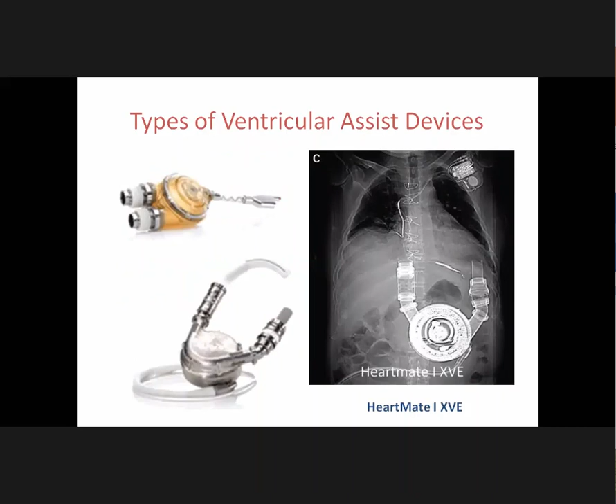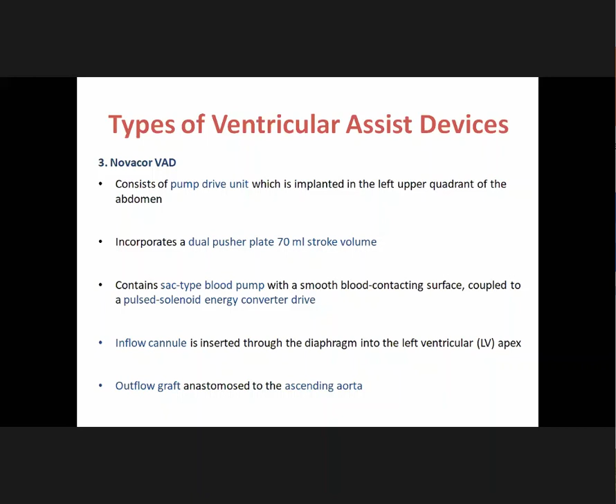This is the HeartMate 1 XVE, which is a large device that is being placed in the abdomen. The third one is Novacor. It also consists of a pump drive unit which is implanted in the left upper quadrant of the abdomen. It incorporates a dual pusher plate of around 70 ml stroke volume. It contains a sac type blood pump with a smooth blood contacting surface coupled to a pulsed solenoid energy converter drive. The inflow cannula is inserted through the diaphragm into the left ventricular apex, and the outflow graft is anastomosed to the ascending aorta.